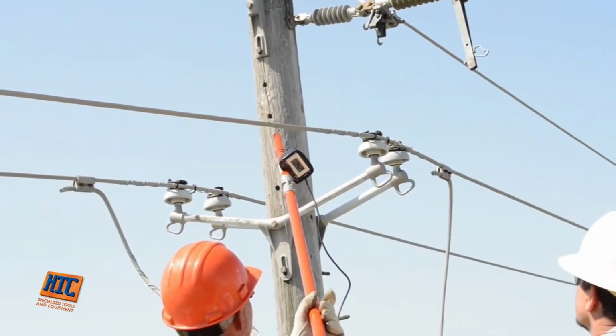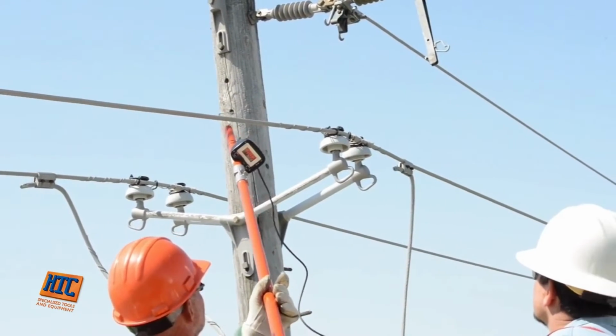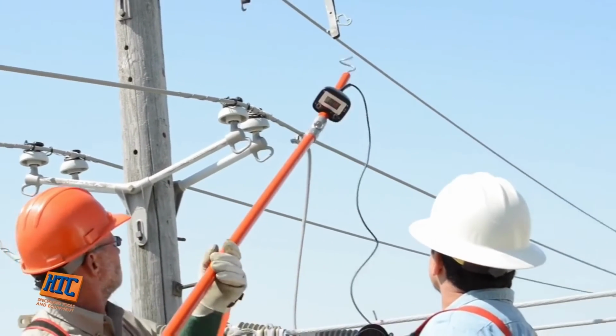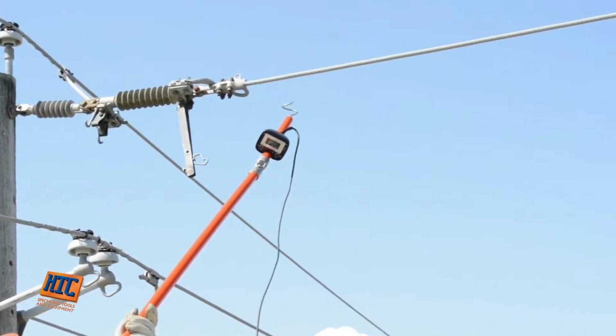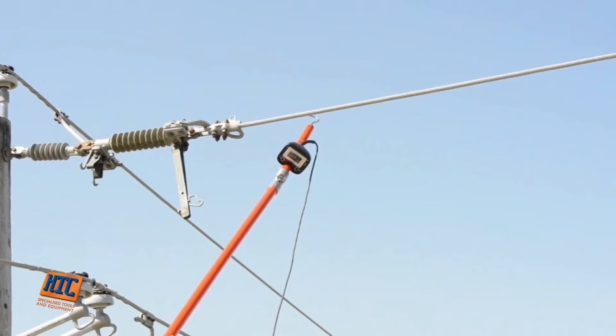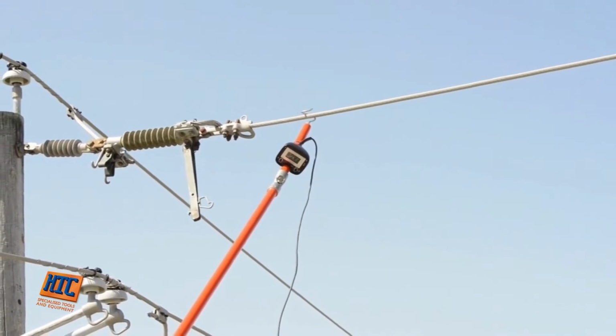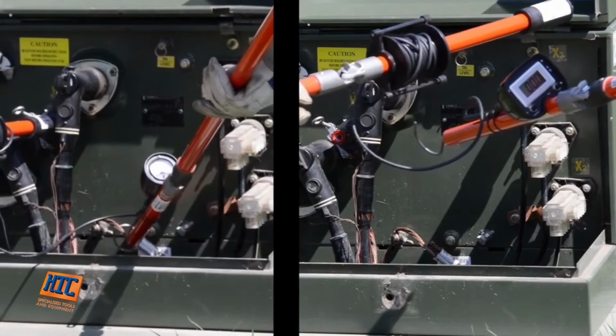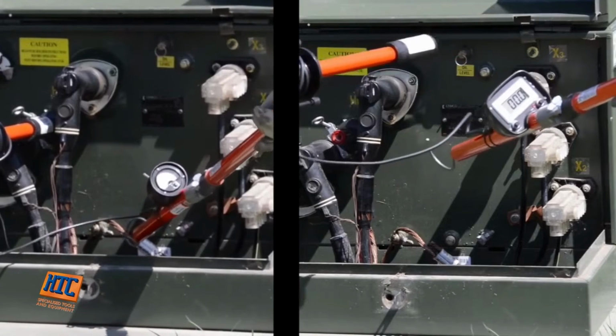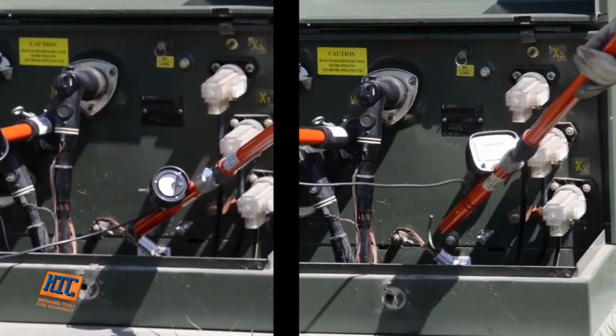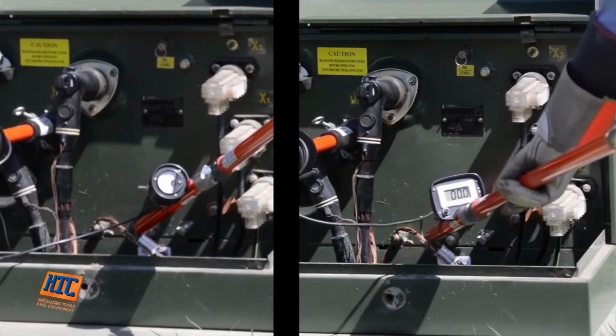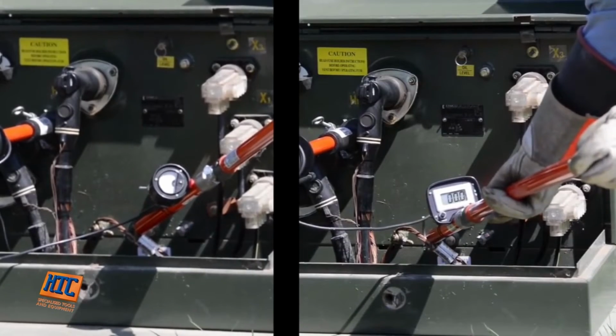Besides being able to determine phase relationships, the digital phasing tester can check overhead voltage, both phase to ground and phase to phase. Here, it displays the actual potential present on this circuit. Both the digital and analog phasing testers can measure voltage on underground systems. Either of the phasing testers can verify that an underground conductor between transformers is de-energized.